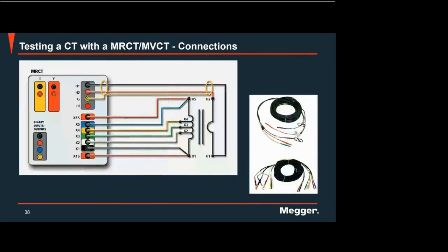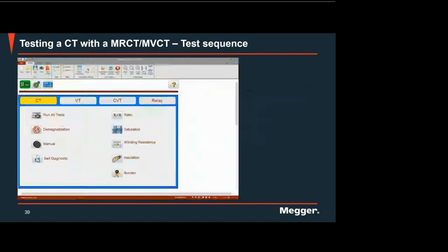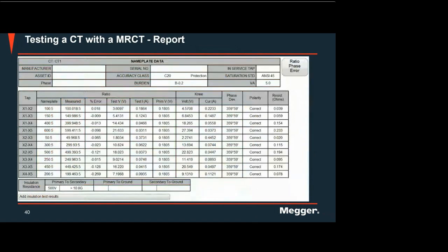Right? And looking at the accessories, as you can see here, we can test 5 simultaneous taps. This is for the MVCT. So same thing, very clear, very easy to understand, and simple. Right? Like I've said, we do test sequence. So when you do the run all test, it will do the tests in a sequential manner. And this is the report here. It will display all the taps, error and ratio. You get the error here. You get the test voltage, you get the test current, you have the primary voltage, and the knee point voltage and the knee point current. You have the phase angle deviation, you have the polarity, and the winding resistance.